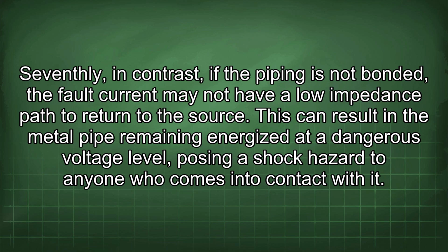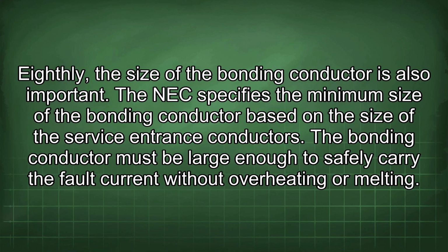Seventhly, in contrast, if the piping is not bonded, the fault current may not have a low impedance path to return to the source. This can result in the metal pipe remaining energized at a dangerous voltage level, posing a shock hazard to anyone who comes into contact with it. Eighthly, the size of the bonding conductor is also important. The NEC specifies the minimum size of the bonding conductor based on the size of the service entrance conductors. The bonding conductor must be large enough to safely carry the fault current without overheating or melting.